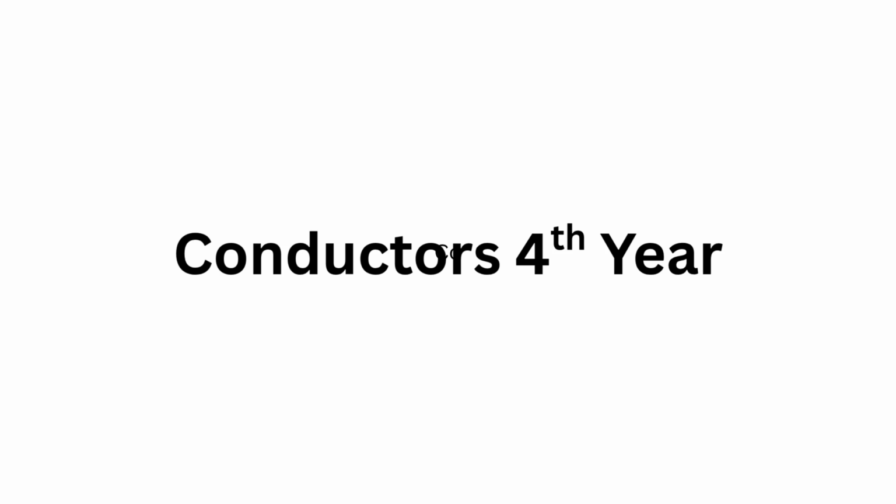Okay, so when you're picking a conductor, the code basically lays out 5 key things you have to satisfy, like a safety checklist. First off, you need the minimum ampacity for whatever load you're running. Makes sense. Second, is the load continuous, running for hours, or is it more on and off? That matters. Third, and this is really important, the max conductor termination temperature, where it connects. Fourth, figuring out the conductor's actual ampacity, considering its environment. And fifth, those specific conditions, like how hot the area is, is it in a raceway, things like that.